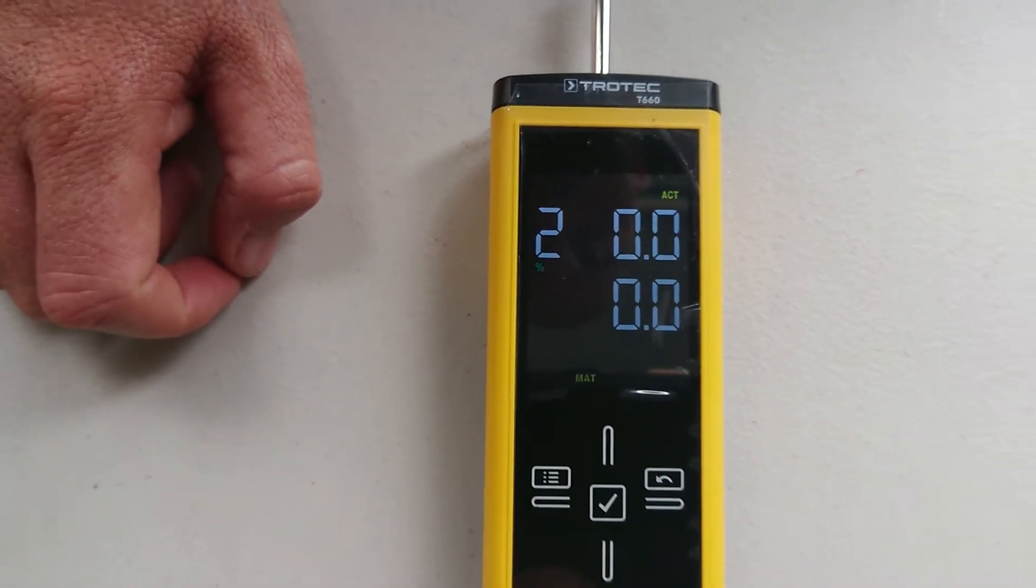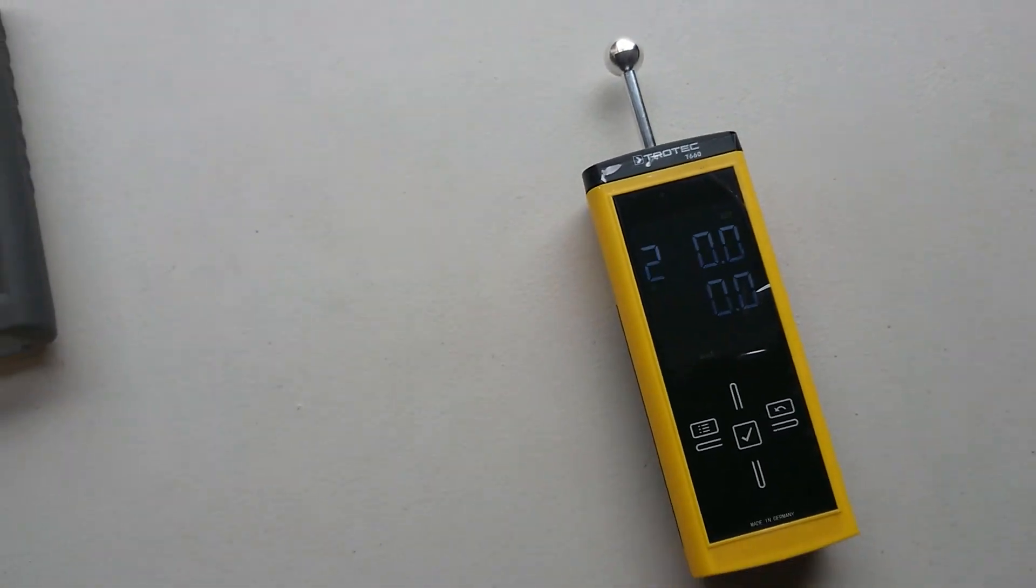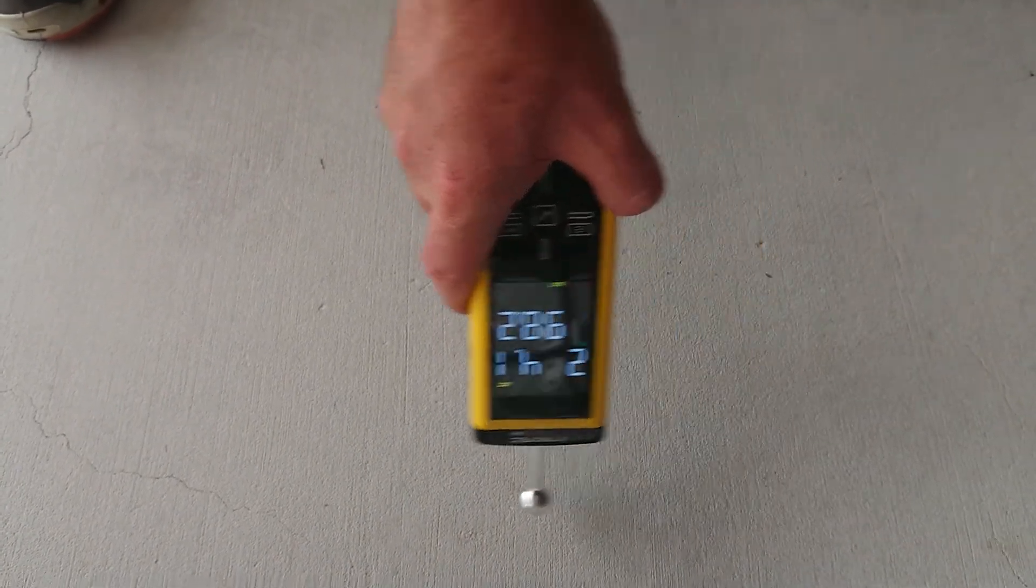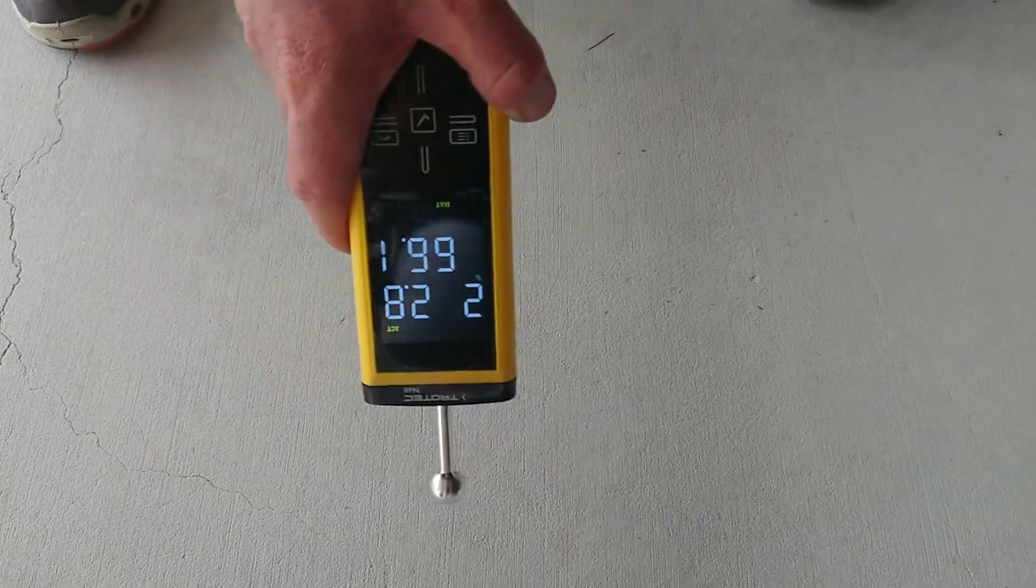So what we have to do with our concrete is if we check the concrete just here behind us, we'll find it's 3.8, 4.0, 5.4. So we really want to make sure we can try to get this under 4.5.